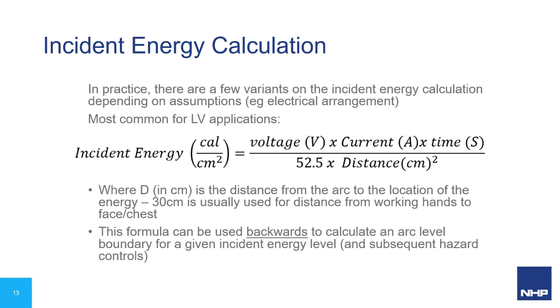The energy will be shaped, directed, deflected, depending on exactly the scenario that it's in. So the flow of energy can be different, but at some point you have to actually come up with something pragmatic that you can actually work with. So this is the incident energy calculation that's most common, and it's probably the easiest to follow as well.